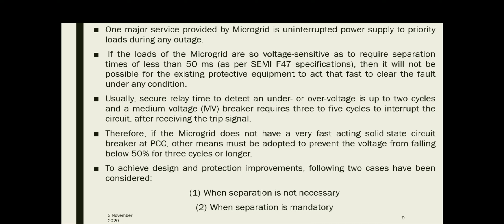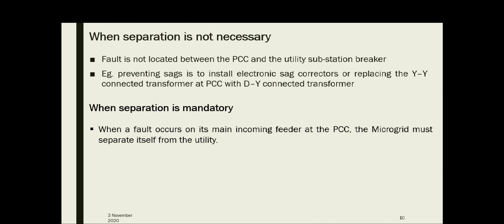Therefore, if the microgrid does not have a very fast-acting solid-state circuit breaker at PCC, other methods must be adopted to prevent the voltage from falling below 50% for three cycles or longer. To design protection improvements, the following cases must be considered: first, when separation of the microgrid from the grid is not necessary, and second, when separation is necessary.